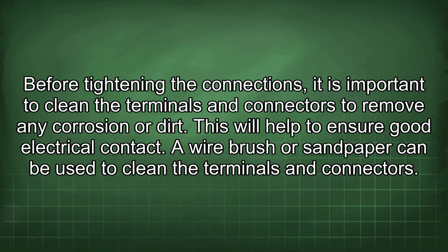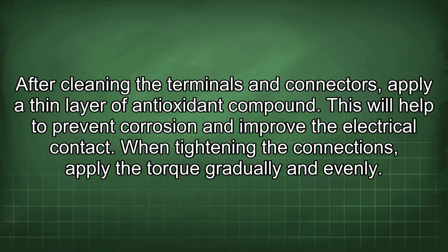Before tightening the connections, it is important to clean the terminals and connectors to remove any corrosion or dirt. This will help to ensure good electrical contact. A wire brush or sandpaper can be used to clean the terminals and connectors. After cleaning the terminals and connectors, apply a thin layer of antioxidant compound. This will help to prevent corrosion and improve the electrical contact.